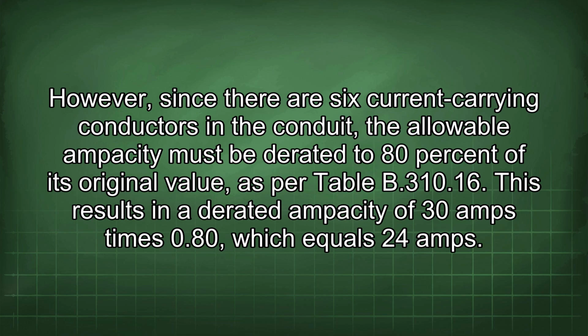However, since there are 6 current-carrying conductors in the conduit, the allowable ampacity must be derated to 80% of its original value, as per Table B 310.16. This results in a derated ampacity of 30 amps times 0.80, which equals 24 amps.